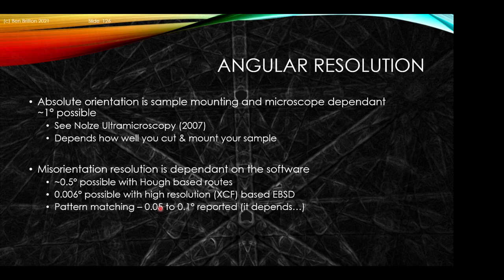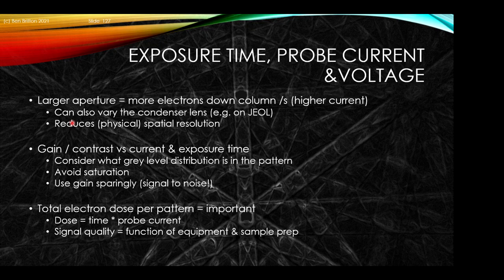It depends a little on a few settings, but point-to-point misorientation is far better than absolute orientation — that's one important aspect. To set up the microscope, a large aperture often enables more electrons down the column, so more electrons per unit time and a higher probe current. In some instruments this may also be achieved by changing the condenser lens settings, which effectively changes how many electrons go down the sample by changing the beam divergence before it goes through the aperture. A large aperture or large condenser current can reduce the physical spatial resolution, so be slightly careful.